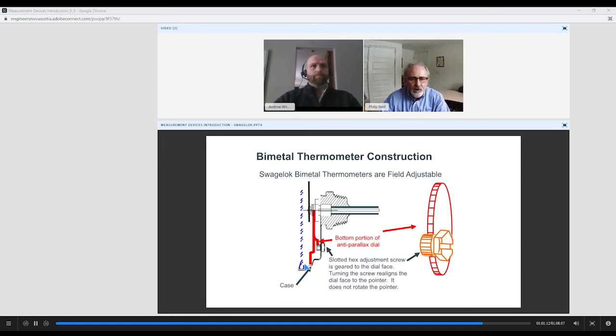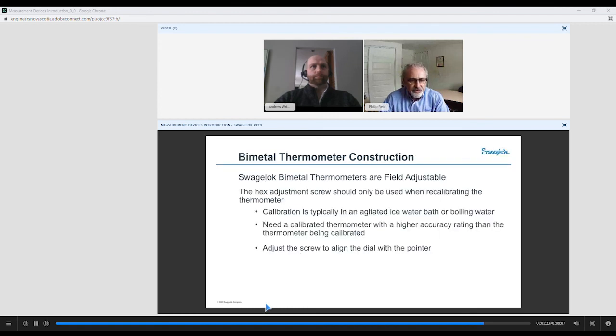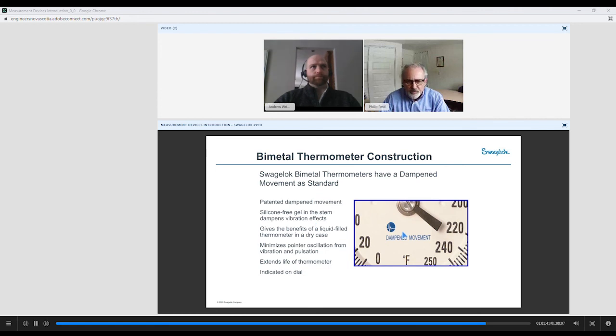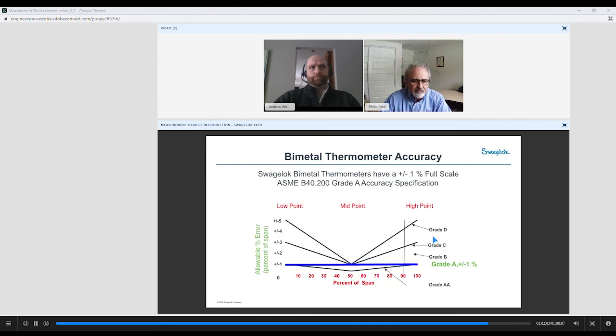Looking a little bit more at how you calibrate, the bimetal thermometer is field adjustable, as you can see. It's got a gear in the back of it that turns and rotates the dial in the face. That is done through the typical methods, either an agitated ice bath or boiling water. You'd want the calibrated thermometer accuracy traceable back to something like NRC or NIST. The patented movement does not liquid fill, but it has a silicone-free anti-dampener, so you don't get oscillation on the needle because of this dampened movement, and that would be on the face. Plus, you're not introducing any other media into the system, so it extends the life of the thermometer.